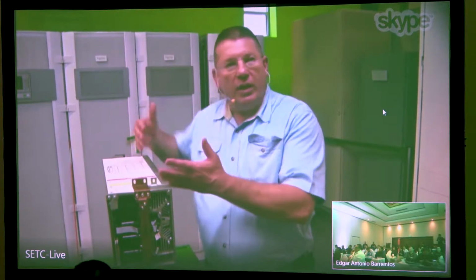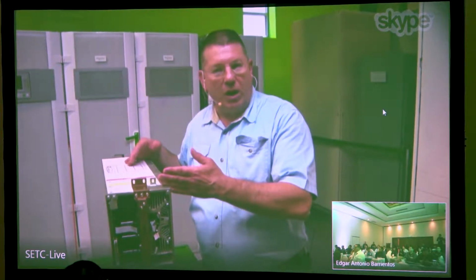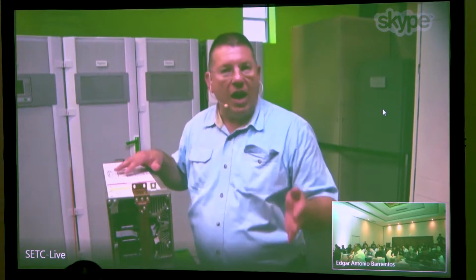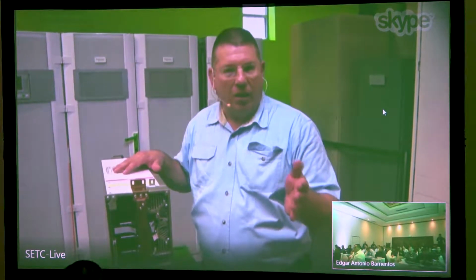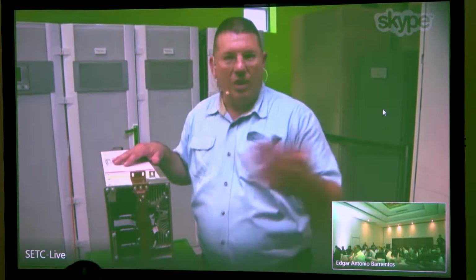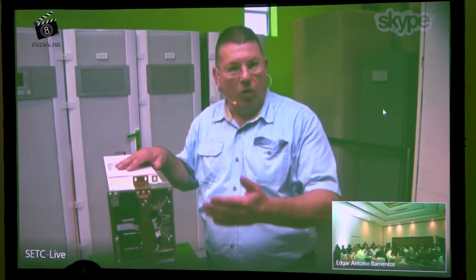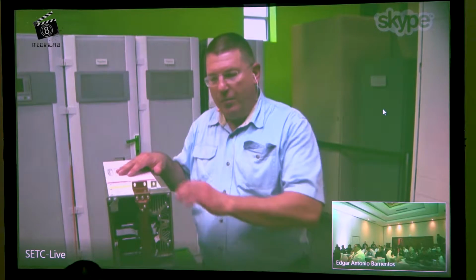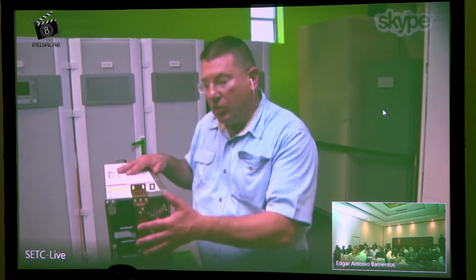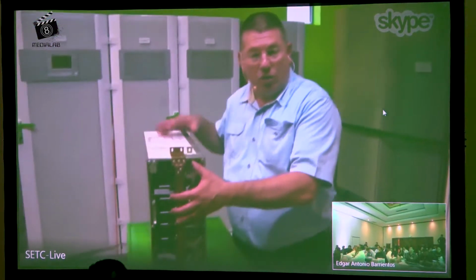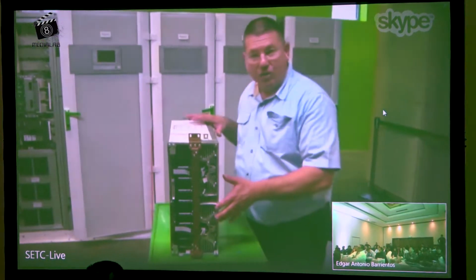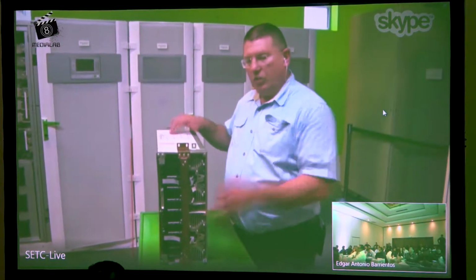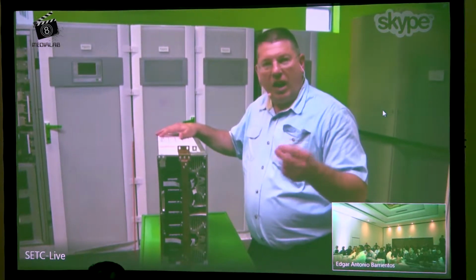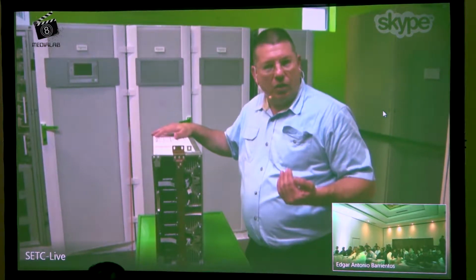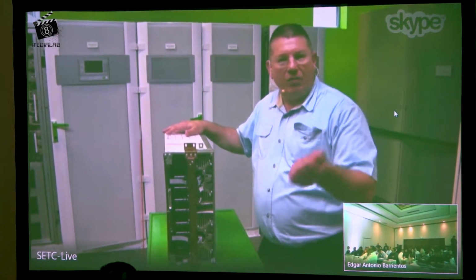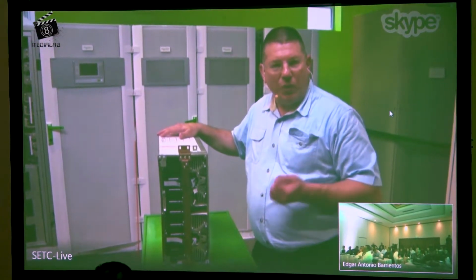Now, we're looking at a 10-year replacement recommendation on this module, but we're not looking at replacement of capacitors at a 5 or 7 year interval like we have on the legacy UPSs. When it's time to replace the capacitors, it's going to be done right here. We're going to pull the module out and revitalize the UPS with a new module. So that's really innovative as well.